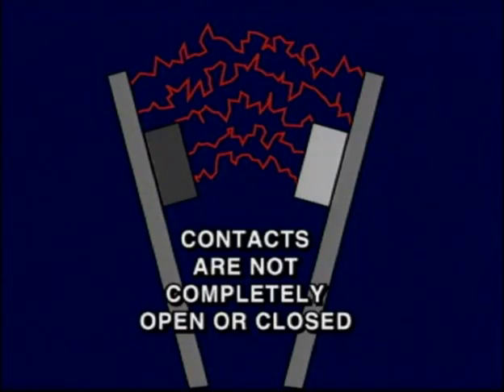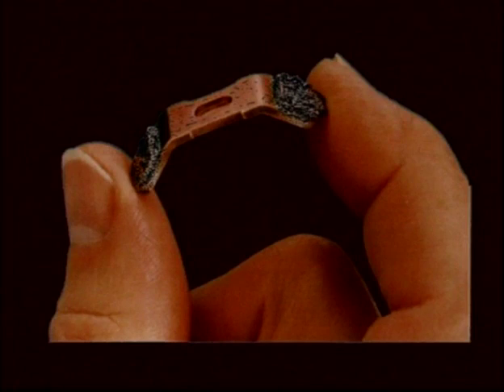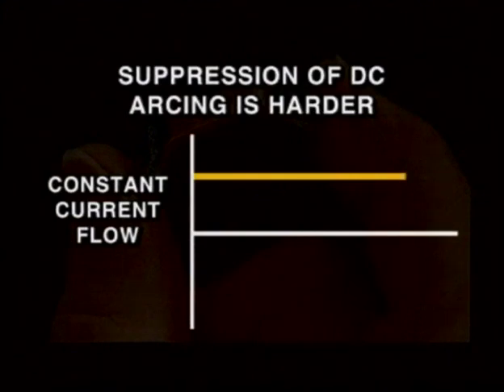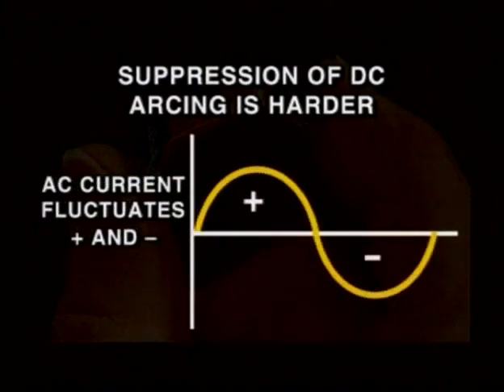This arc can continuously create heat, which can eventually damage the contact surface. Since prolonged arcing can damage the contacts, the sooner this arcing is extinguished, the longer the contactor will last, and there are several methods used to suppress the arcing. Suppression of DC arcing is harder to eliminate because the DC supply continuously provides flow of current in one direction instead of fluctuating, like AC does, between positive and negative.